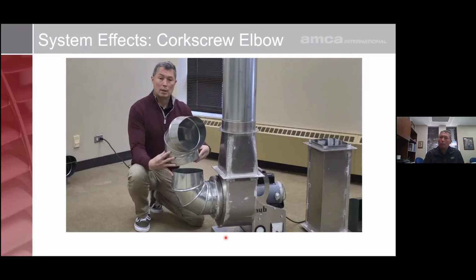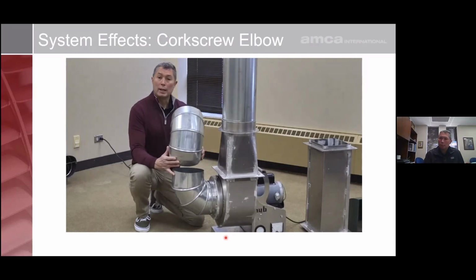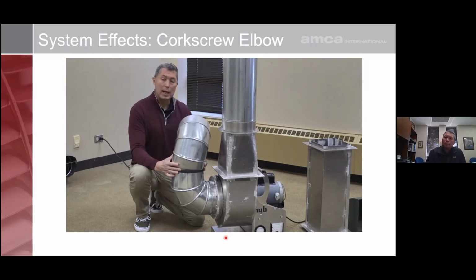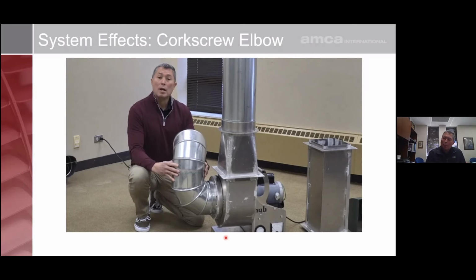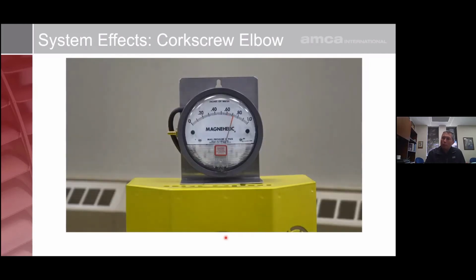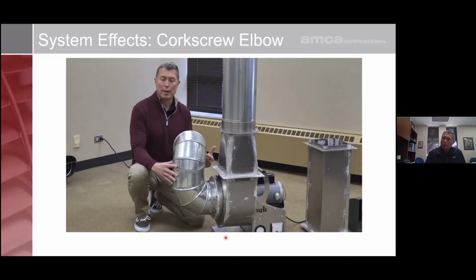Now when I turn this 180 degrees, kind of listen to what's happening. I put it on here, the fan gets much noisier, sounds a little bit rougher, and also the magnehelic is showing the pressure went up as the fan's operating. So that extra noise is basically, we're now counter-spinning the air as it enters the fan. Air is going in the opposite direction of the wheel rotation, kind of like when you're rolling down the driveway backwards, put your car into gear, push it forward, it effectively moves, but it does it in a very rough manner. Same thing happens with the air as it enters and discharges the fan.